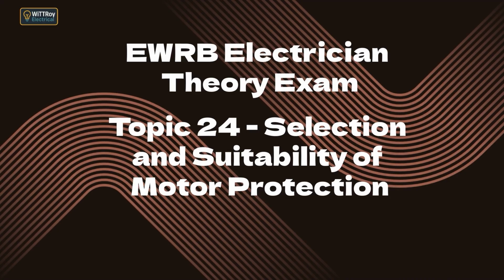Topic 24d. Explain backup protection and discrimination with respect to protecting motor circuits. Backup protection. Backup protection is a second protective device that operates if the first one fails or cannot clear the fault. For example, if an overload relay trips too slowly during a short circuit, the upstream circuit breaker must trip to protect the cable and motor.